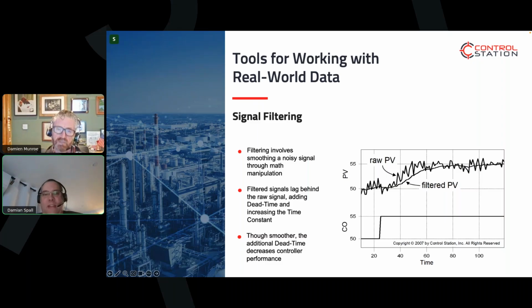So working with real world data, signal filtering is obviously really important. Without wanting to state the obvious, just to go over some key points: filtering involves smoothing a noisy signal through math manipulation. Filtered signals lag behind the raw signal, adding dead time and increasing the time constant. Although smoother, the additional dead time decreases controller performance, as seen in the visual.